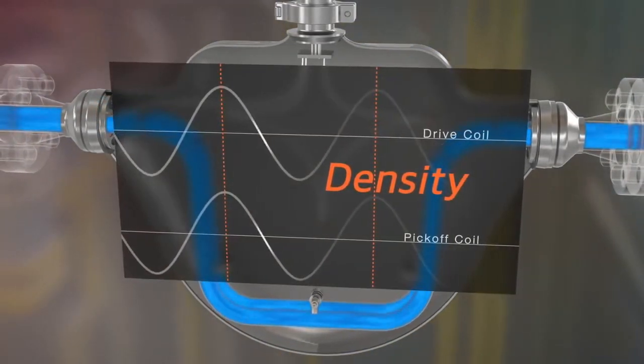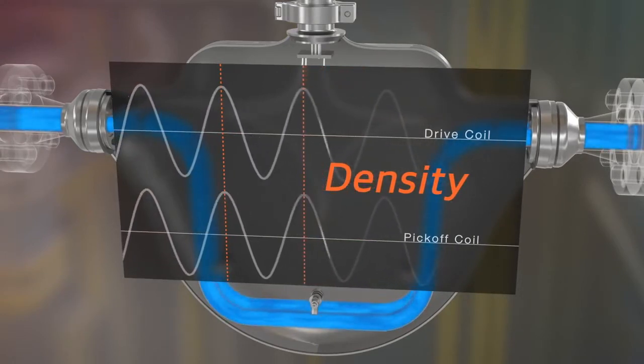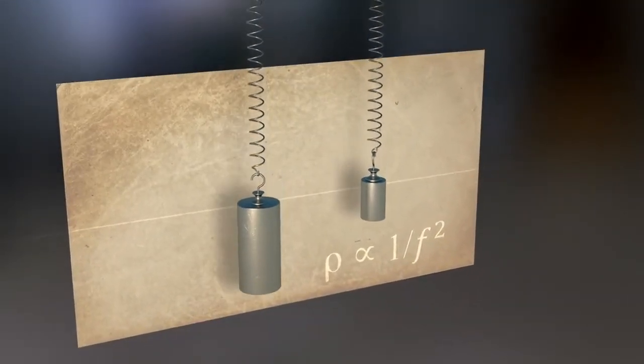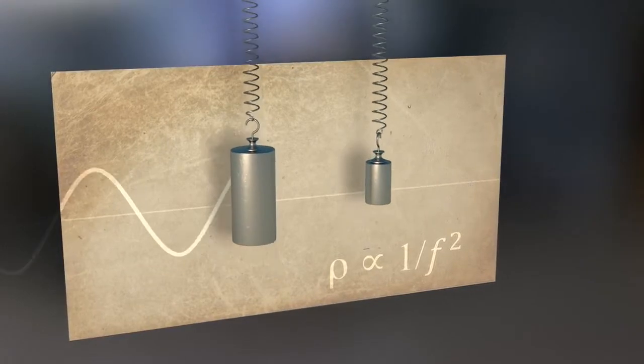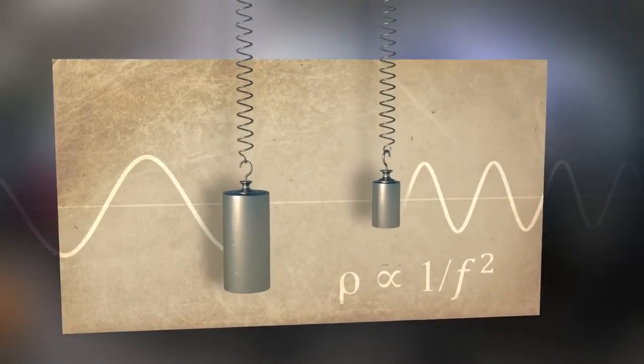When the liquid density changes, the vibrating frequency of the tubes also changes. Similar to a spring and mass system oscillating at its natural frequency, a larger mass oscillates at a lower frequency, while a smaller mass oscillates at a higher frequency.